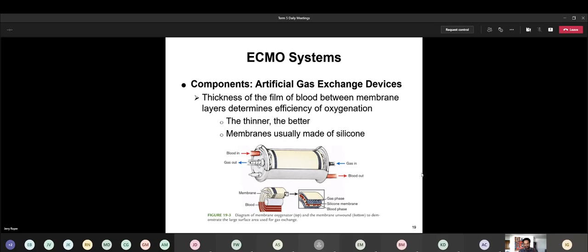The membrane itself. Well, the membrane, the silicone that they use, there's layers essentially, and the blood is going to pass through one of those layers, and it's the thickness of the blood film that's going to make the difference between a membrane oxygenator that works very well and one that doesn't work that well. So the thinner that you make that film of blood, the more surface area you're going to have for gas diffusion to take place. And that's how you're going to get the best oxygenation and ventilation, really. So a lot of times, one membrane oxygenator may work a little bit better than another company's because the first company found a way to make those layers of blood between them very, very thin.